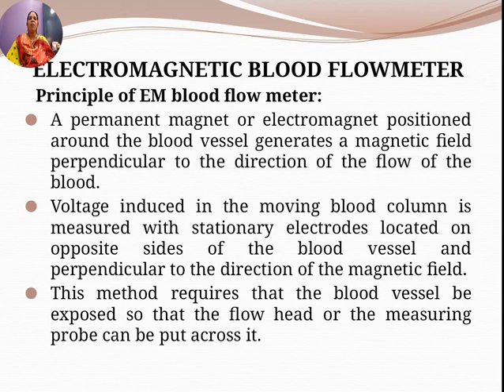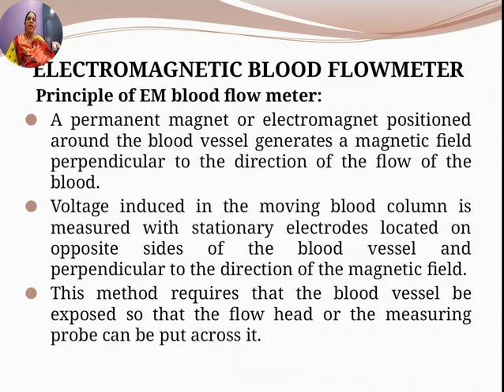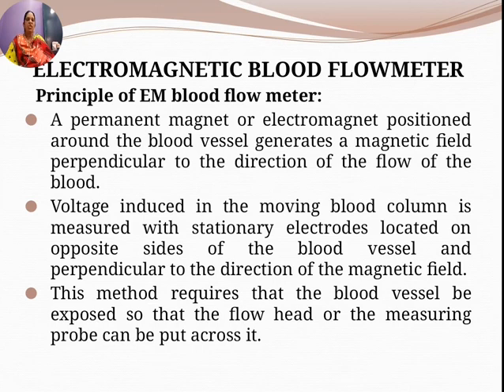The voltage induced in the moving blood column is measured with stationary electrodes located on opposite sides of the blood vessel, perpendicular to the direction of the magnetic field. This method requires the blood vessel to be exposed so that the flow head or measuring probe can be placed across it — making it an invasive method. Because of blood movement through the vessel, an EMF is induced perpendicular to the direction of the magnetic field.